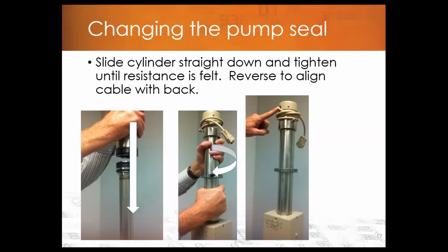Once you've got it tightened down into the cylinder mounting block, go ahead and tighten it down all the way that it will go. And then what you want to do is back it off in your counterclockwise direction just enough so that your pressure transducer at the top is positioned so that your cable on the transducer is coming straight out the back and your ports are lined up on your left and right side.